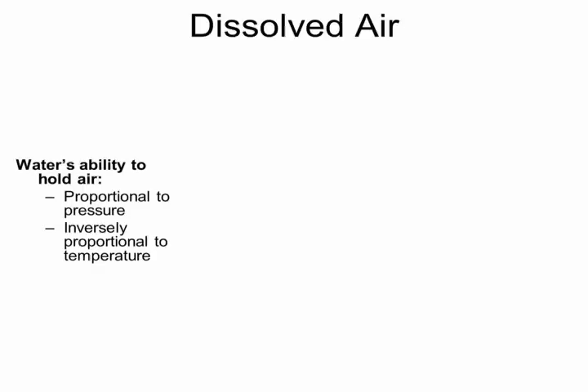So dissolved air in water, how does it perform? Well, water's ability to hold air is, one, proportional to pressure. The more pressure you have on your system, the more that system will keep that air in check in solution. And it's inversely proportional to temperature. So proportional to pressure, you can picture the effects of that: you take a bottle of beer, the beer's under pressure, you open up the cap, and all of a sudden you see gases come out of solution and bubble up. That's basically that phenomenon.